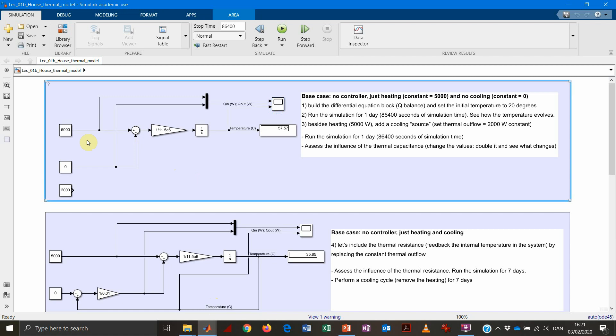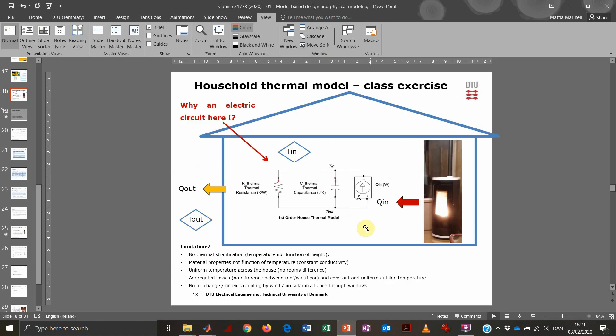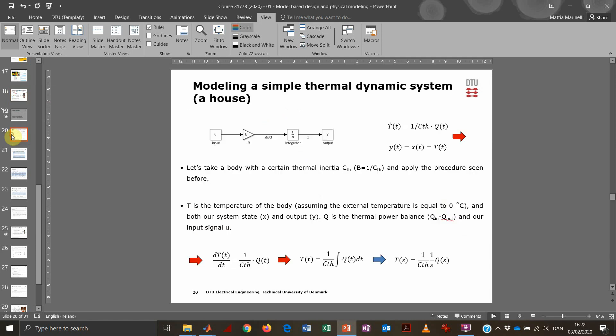We start by representing the simplest subunit — the capacitor subject to a thermal flow. We implement the differential equation: the derivative of temperature over time equals 1 divided by the thermal capacitance, times the thermal power. This is the same form as an electrical capacitor equation. In Simulink, we use a simple block diagram with an integrator. The input is a constant 5000 divided by 11.5 million — representing 5000 W of thermal power and a thermal capacitance of 11.5 million Joules per Kelvin.